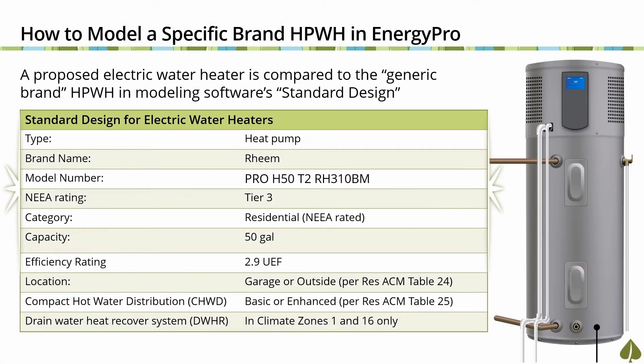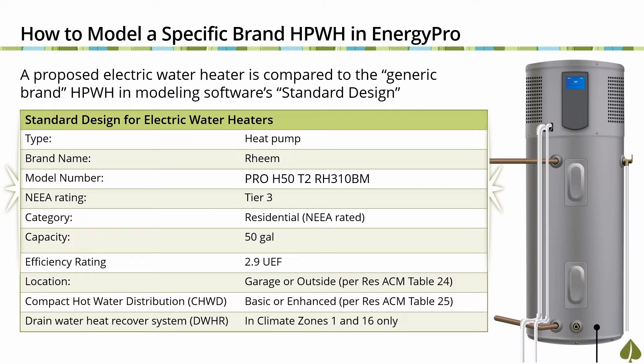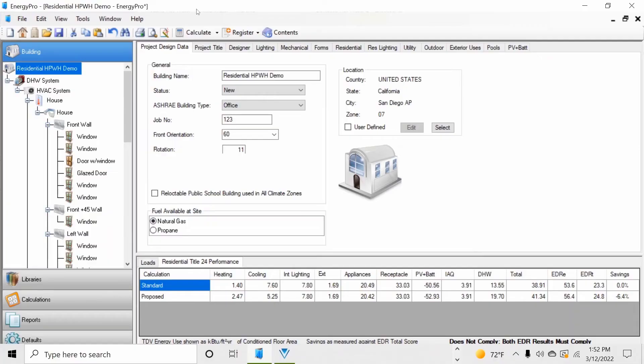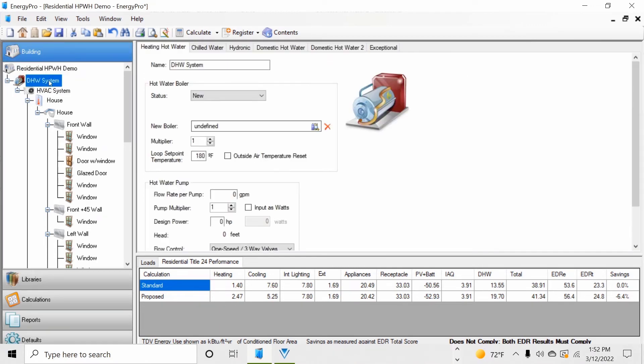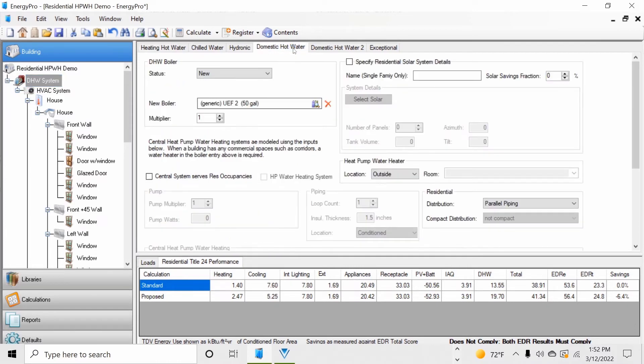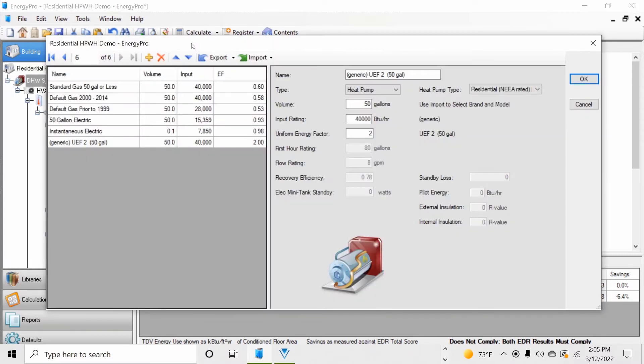To receive a compliance credit for a heat pump water heater requires using a specified make and model number unit which must be listed on the NEEA advanced water heater specification qualified products list as a tier 3 or higher rating. Let's demonstrate how to input a Rheem model number PRO H50 T2 RH310BM unit in EnergyPro. We're back in our EnergyPro demonstration file. First thing you want to do is select the DHW system from our model tree then select the domestic hot water tab and next select the new boiler button. This will reopen the library of water heaters in EnergyPro.